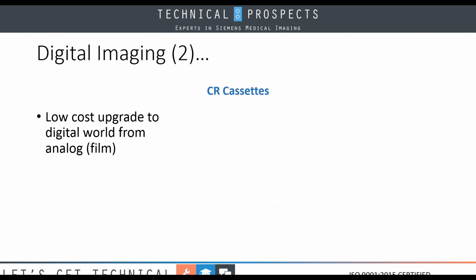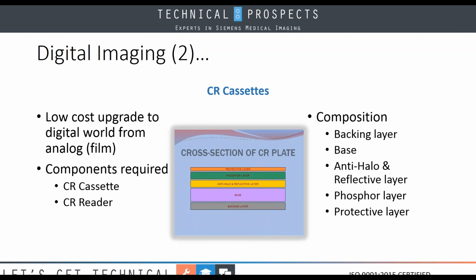Starting off at cassettes, as I alluded to earlier, this was the low-cost upgrade to the digital world from the analog film. It required two components, that of a CR cassette and a CR reader. Now the cassette basically here had its composition, and here you can see the cross section of the CR plate. You have the backing layer, the base, the anti-halo reflective layer, the key one being the phosphor layer, because the phosphor held the image that it received from the light from the intensifying screen that is part of the CR cassette. And then you had a protective layer that was used to protect the overall phosphor.